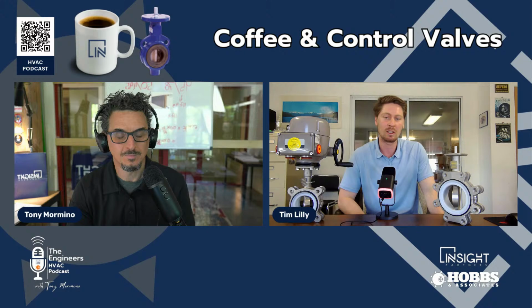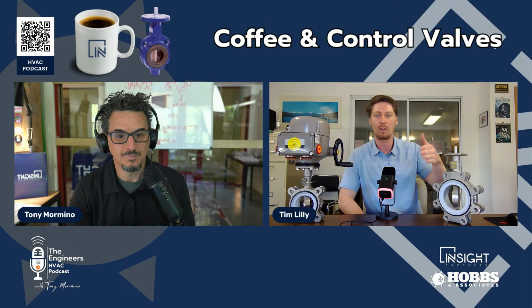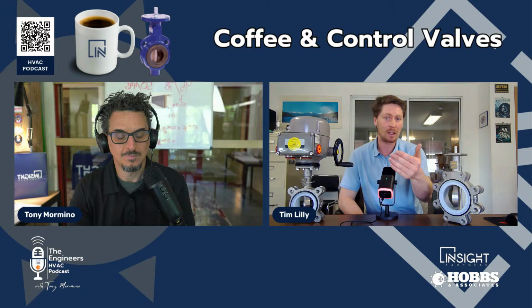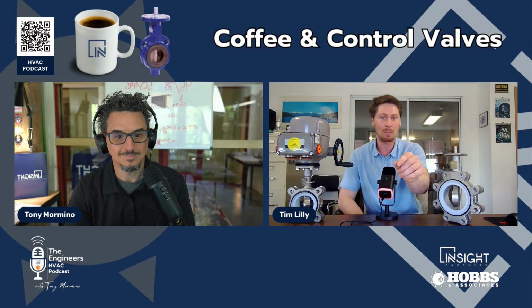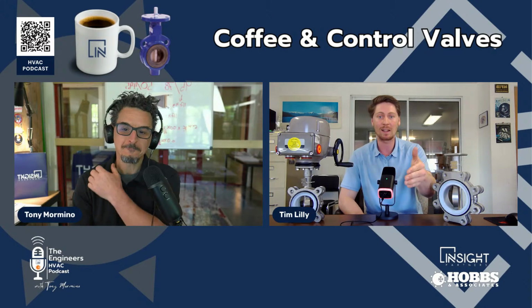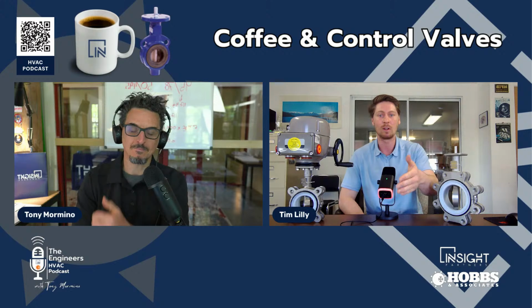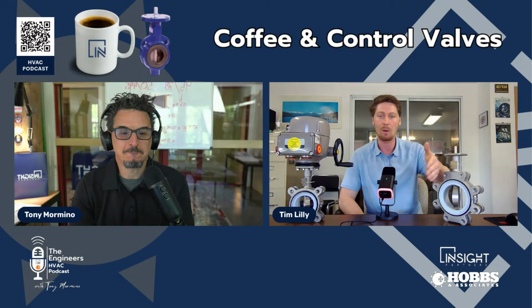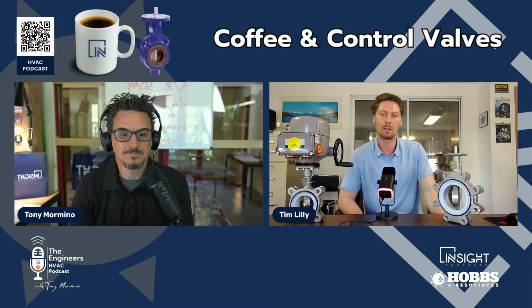Or you can just see it not operating on that curve, and now you've come off your PID loop, you lose your set point. Let's say you're making chocolate truffles and you need the inside to be the perfect temperature going into this truffle so it doesn't crack the exterior or melt the exterior. You have to be right on that set point, so you have to operate on that curve. So if your input changes or your output changes, you need a valve that can stay on that curve.